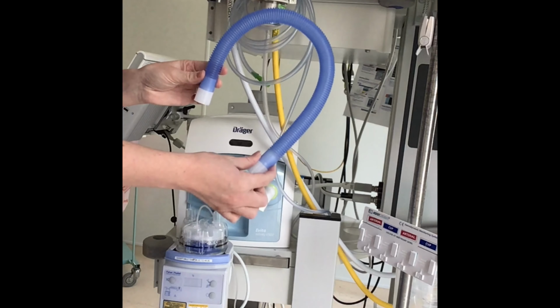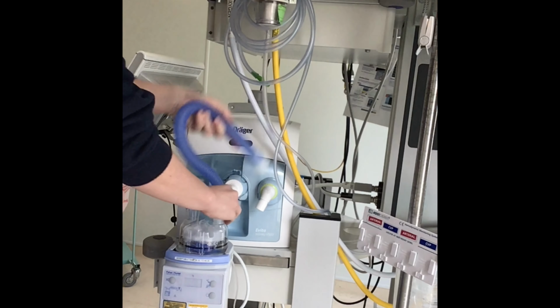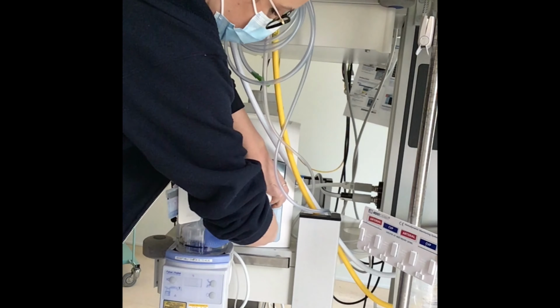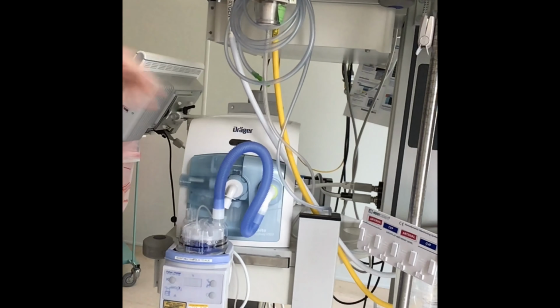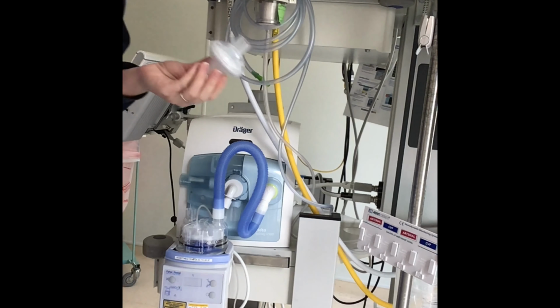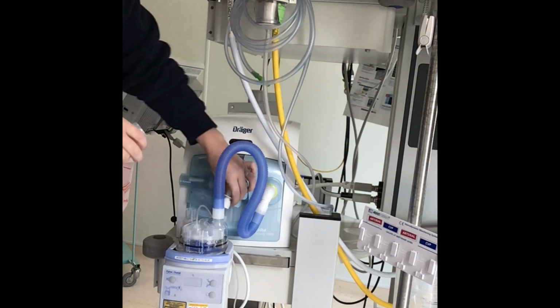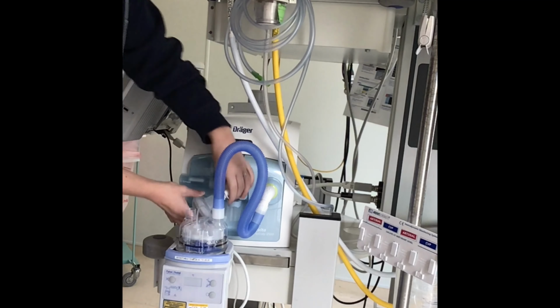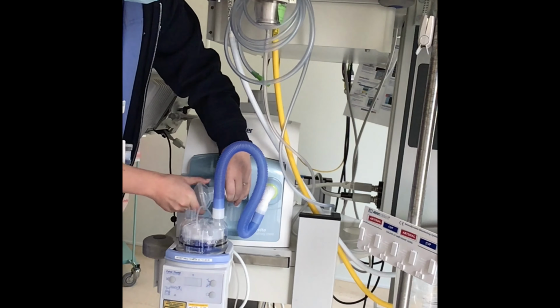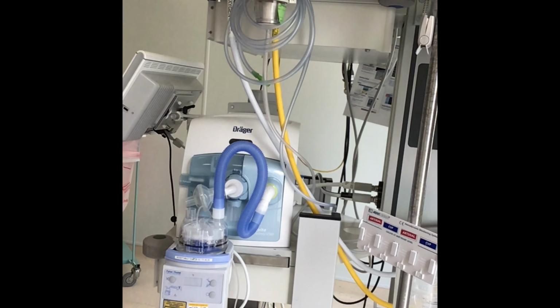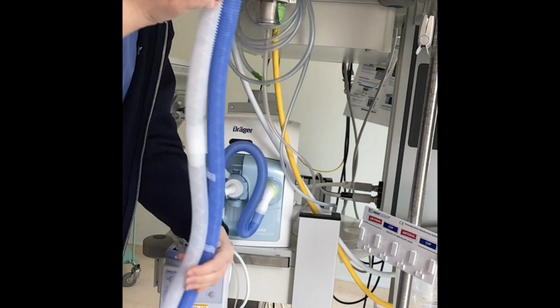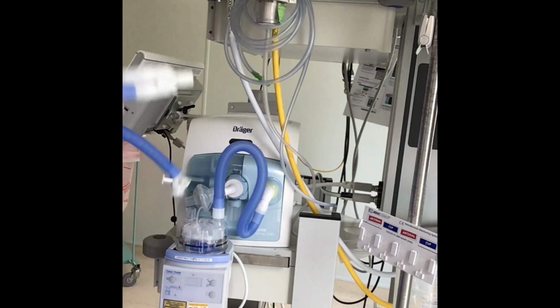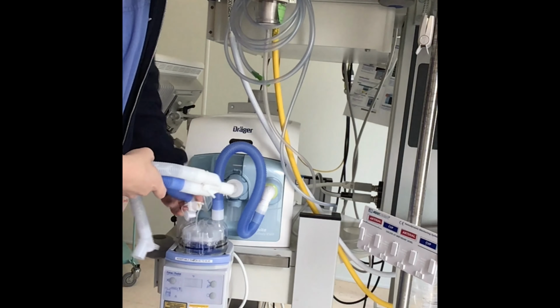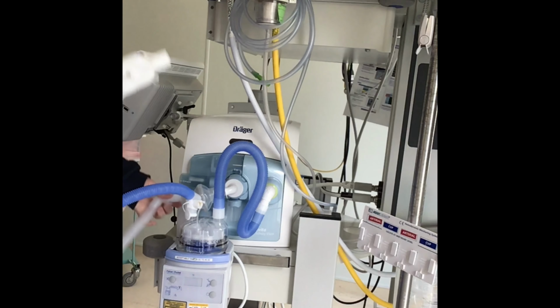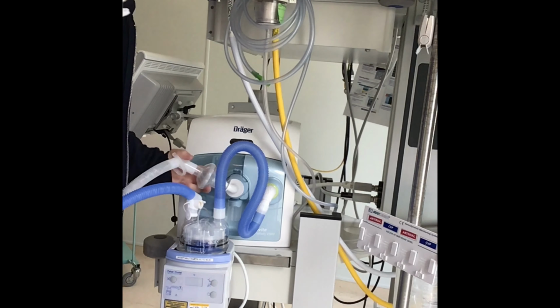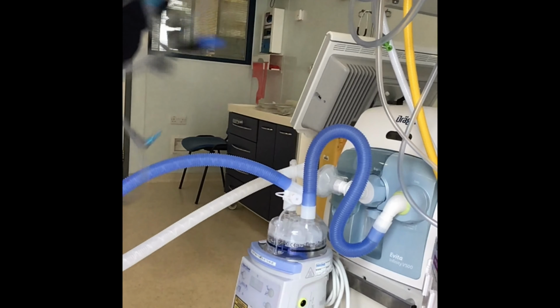You've then got a short piece of tubing, so this will connect onto here, and your inspiratory port. You're then going to put either a viral filter or a bacterial filter on the expiration port to protect the ventilator. Then you've got two bits of tubing that will go to the patient. So blue tubing will always go onto the water bath, and the white tubing will connect to the expiration valve. You can then connect your humidifier cables.